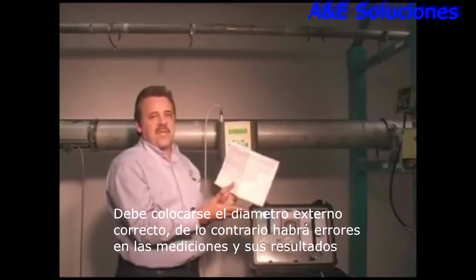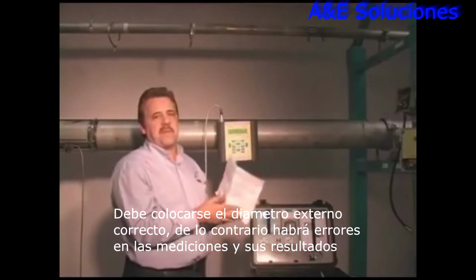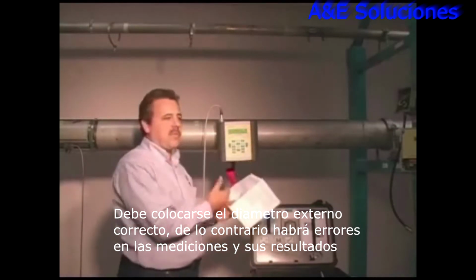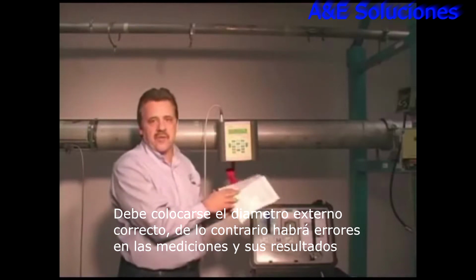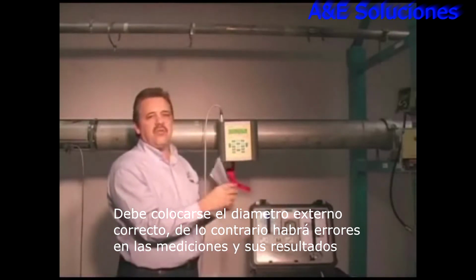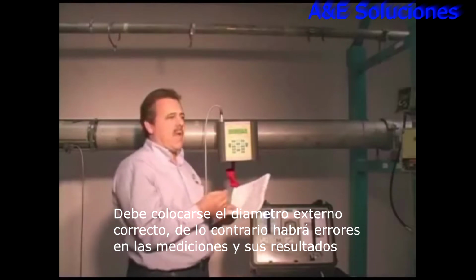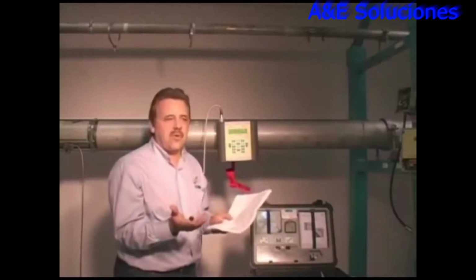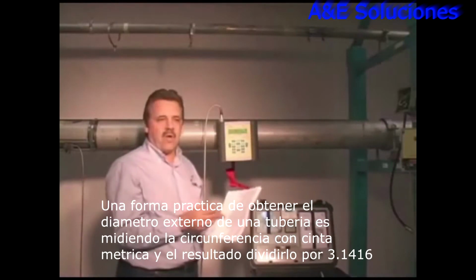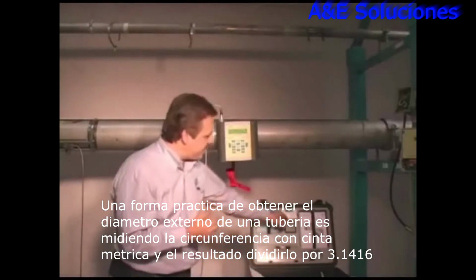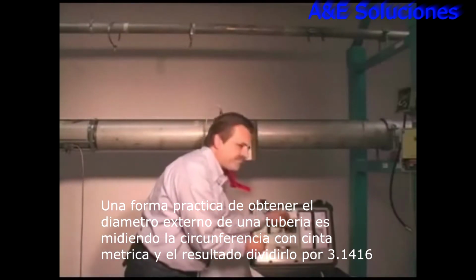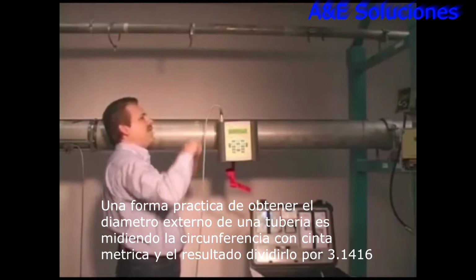I just want to emphasize that, because one of the common mistakes that people make when they're programming the meter is they'll put in 6 inches as the OD. So make sure you're putting in the true outside diameter of the pipe. One thing you probably want to do is to just verify what that is. Take your tape measure and wrap the tape measure around the pipe.